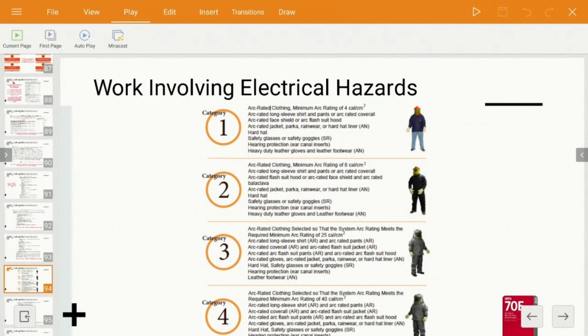Now, if the label on the equipment says, the engineer says, well, the intensity in this panel is going to be 5 calories per centimeter squared. Take that example and times it by 5 over 80-90% of your body. That's a bad burn, right? Yeah, it's a bad burn. Okay, so whenever you see calories per centimeter squared, the different arc flash categories are rated for different intensities of an arc flash if it occurs. Okay?